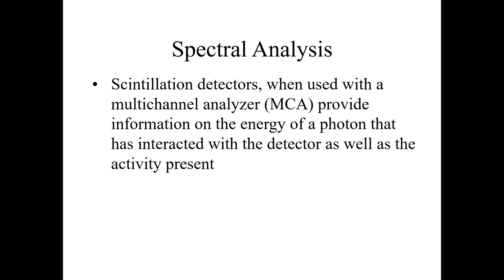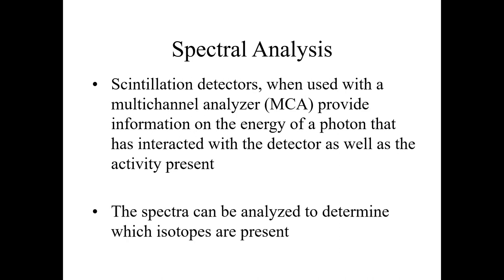We can also perform spectral analysis with scintillation detectors when used with a multi-channel analyzer, abbreviated as MCA. This provides information on the energy of photons that have interacted with the detector as well as the activity present. The spectra can be analyzed to determine which isotopes are present, making it a good choice for isotope analysis.